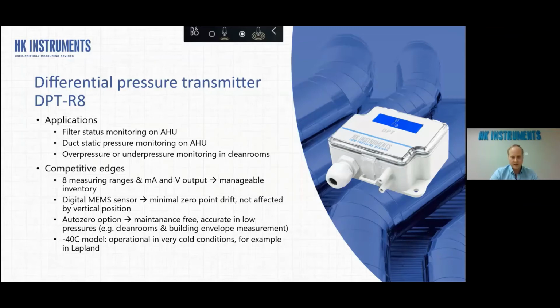And also one good benefit is that it's not affected by vertical position, because the sensor element itself is so small that gravity doesn't have an impact on it. And we have an optional feature on this one, the auto zero option. It really means that the zeroing of the device is done automatically every 10 minutes. So basically, zeroing is the only thing you need to do as a maintenance task. When the auto zero is doing that automatically, you don't have to do it anymore. So it's making the device basically maintenance free. And at the same time, it's increasing the accuracy a bit. So if you are using it in clean rooms, for example, that's highly recommended.